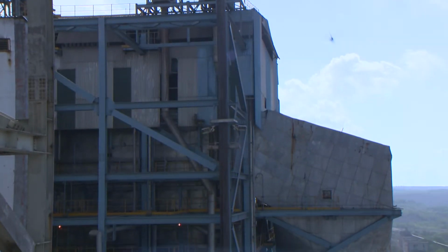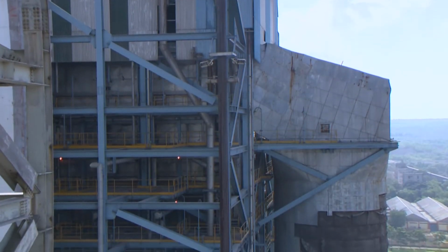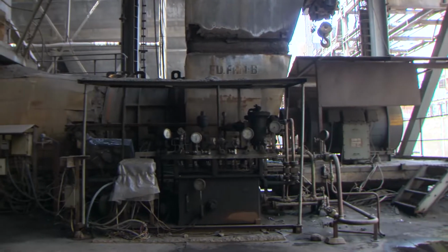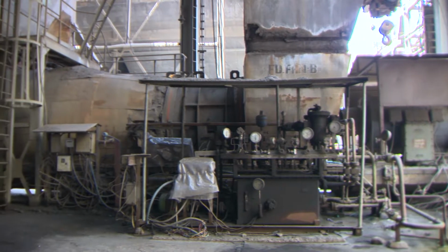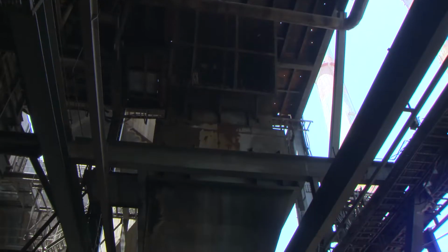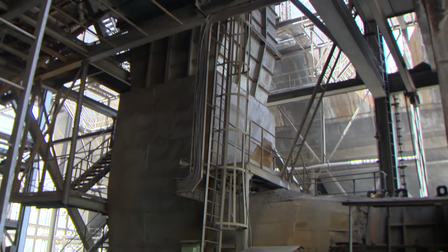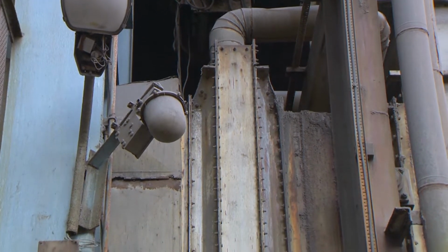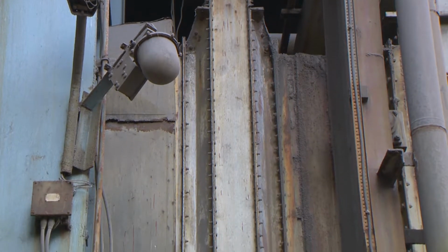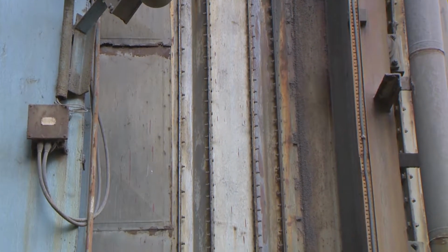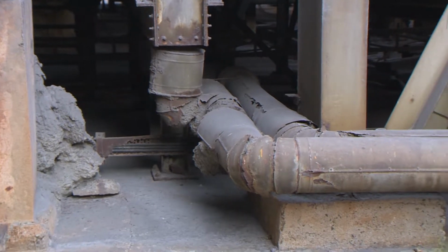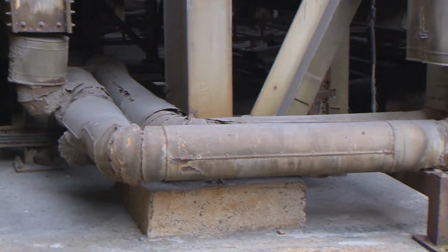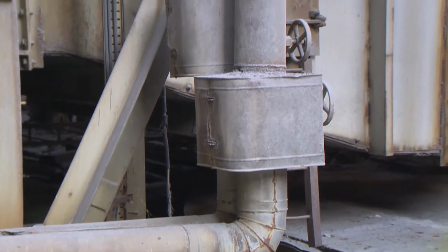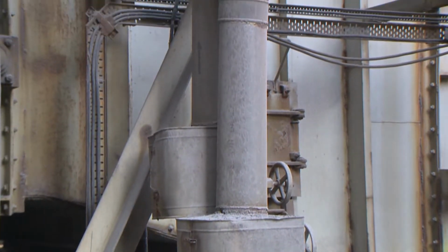Draft system. Balanced draft system is adopted in the boiler. The forced draft fan of axial flow, variable blade pitch control type, sucks air from the atmosphere and supplies it for combustion. The steam coil air preheater is placed at the outlet of the FD fan to increase the air temperature during initial light up of the boiler. The steam taken from the auxiliary steam header is used for heating the air passing through the steam coil air preheater.